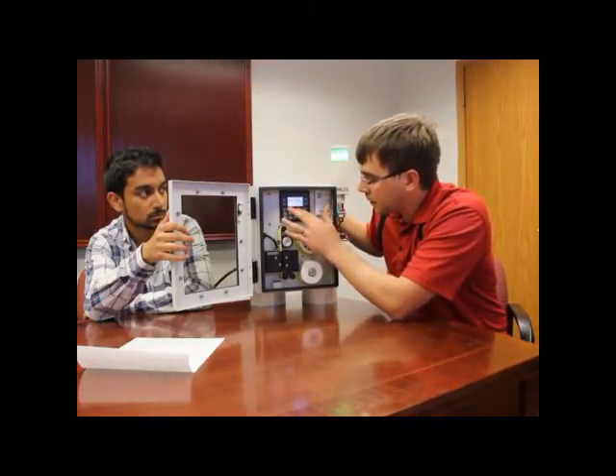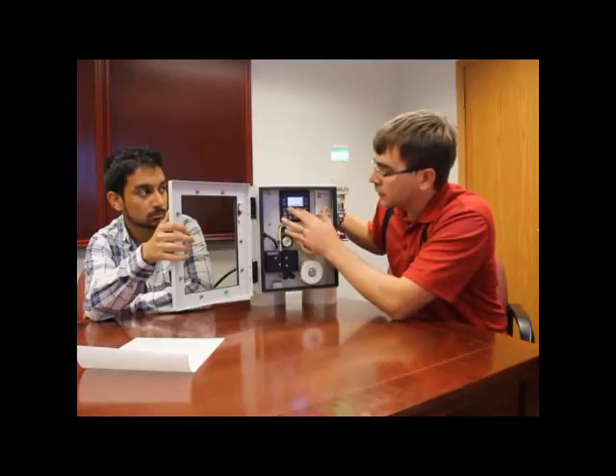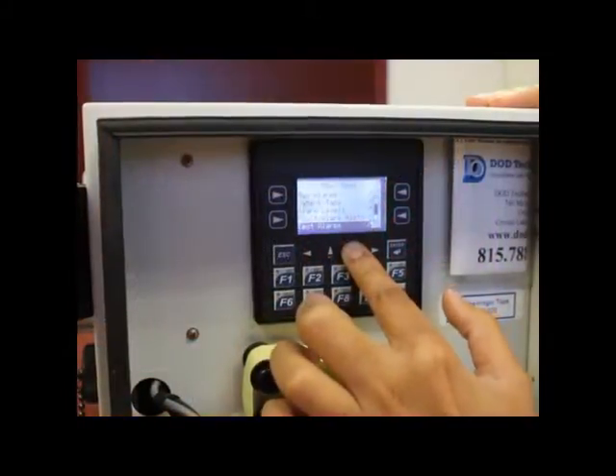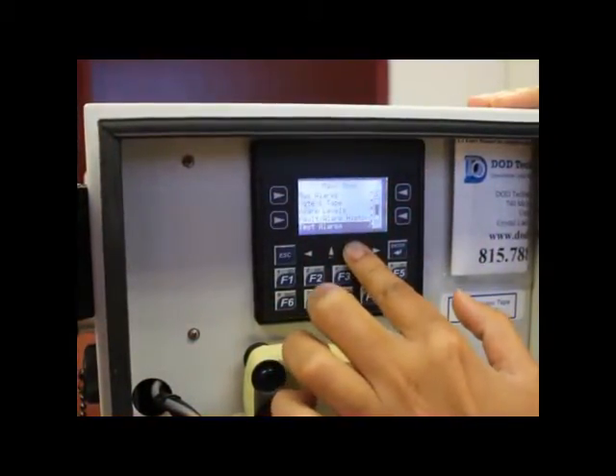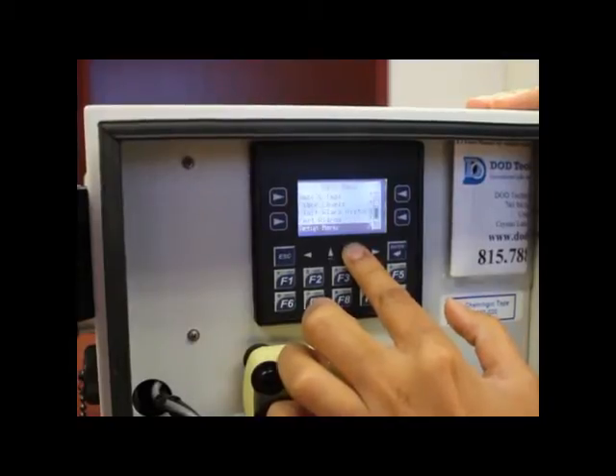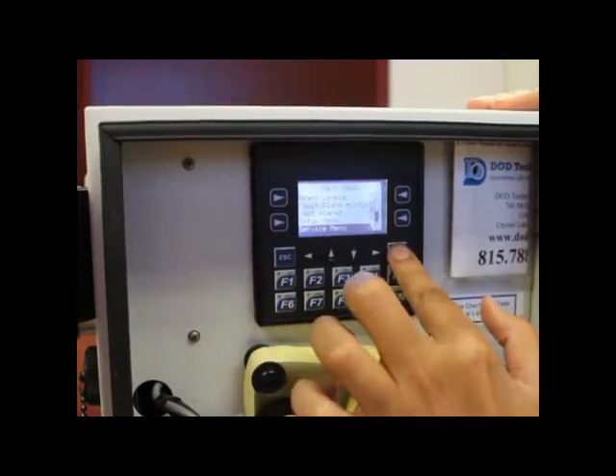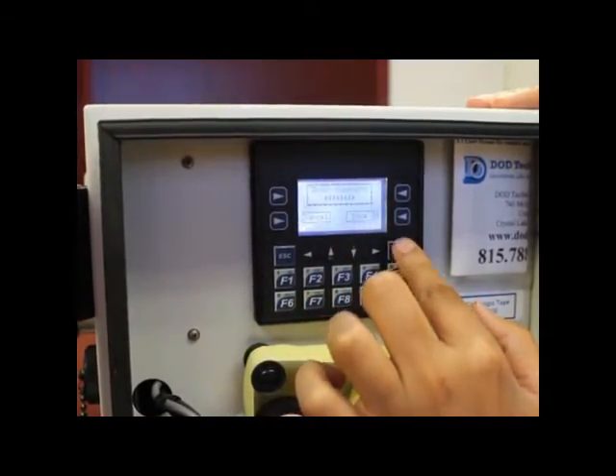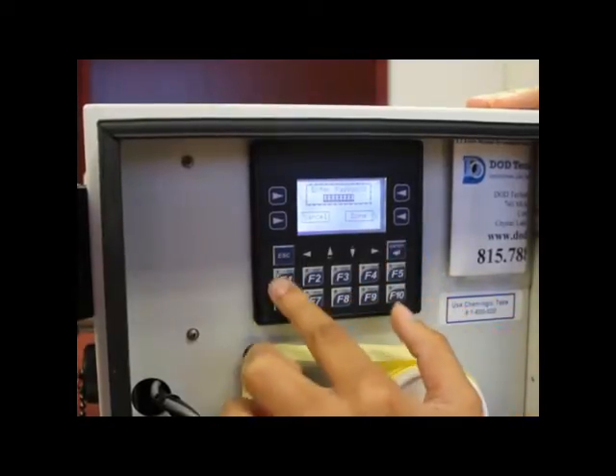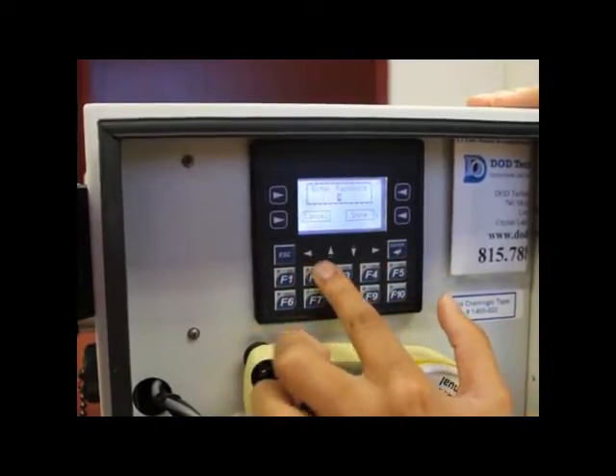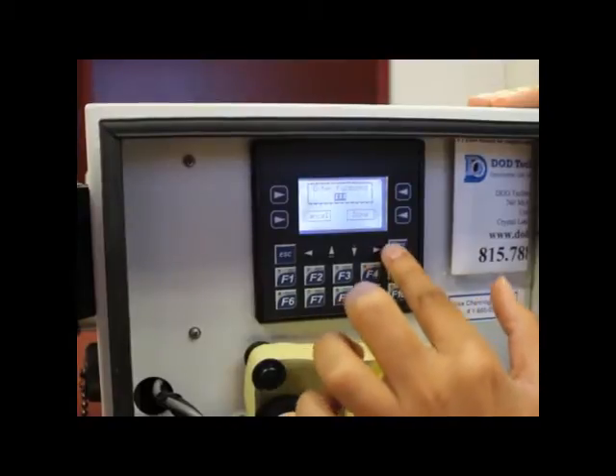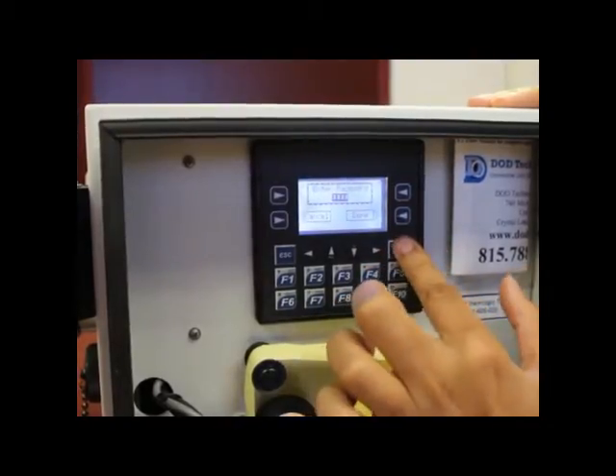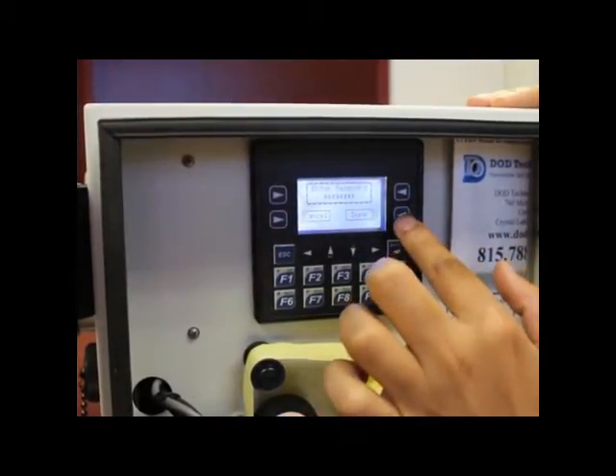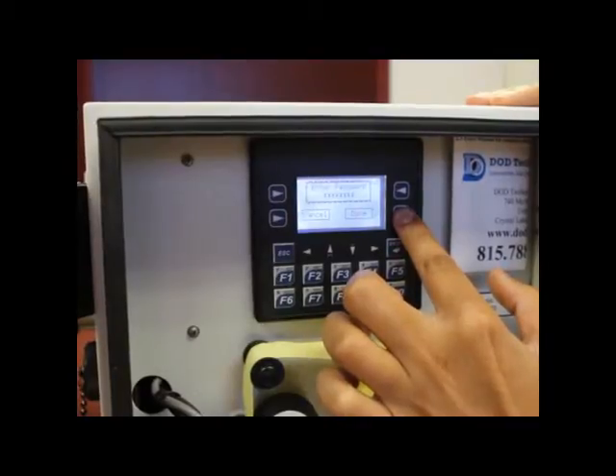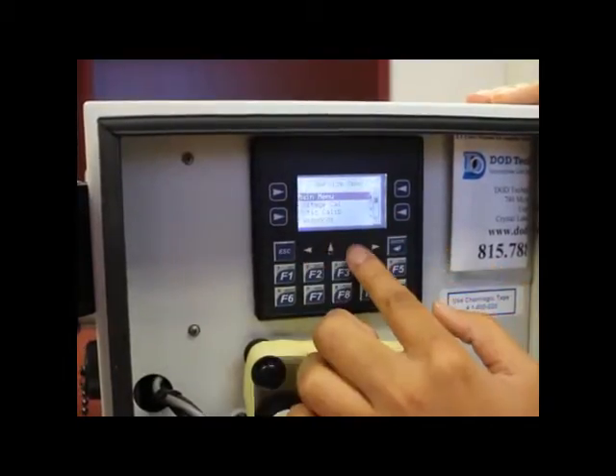Now you have to go down to the maintenance menu, or service menu, I apologize. Click enter, that'll highlight the enter password field. 1, 2, 3, 4, enter. Done. Now you can go to optic calibration.